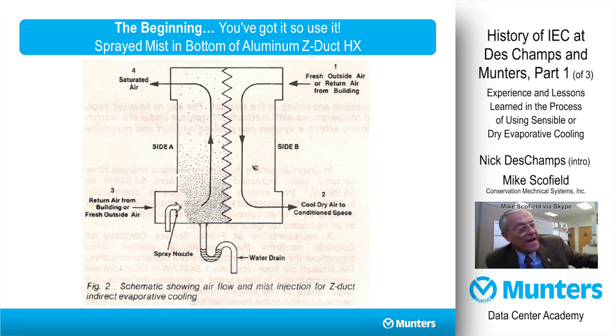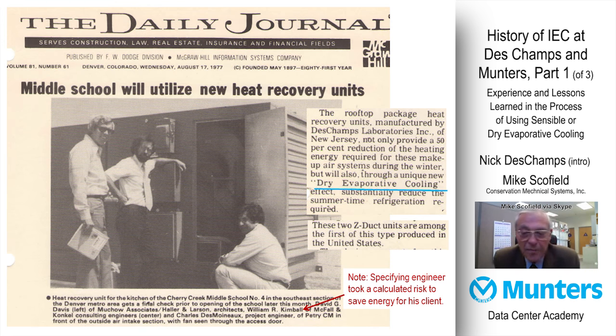So an interesting application came up in 1977, and the next figure shows a write-up that I obtained in the Daily Journal Dodge report on the Cherry Creek School District, which by code had kitchen units and locker room units that required 100% outside air. Bill Kimball of McFall, Conkle and Kimball was the consultant engineer, and I went to Bill. Kind of an interesting story, and I didn't tell him we had test data. I said, "Look, it's pretty intuitive, Bill. If we spray water on the exhaust or scavenger air side of this 60% effective air-to-air heat exchanger, that will increase the sensible cooling effect."